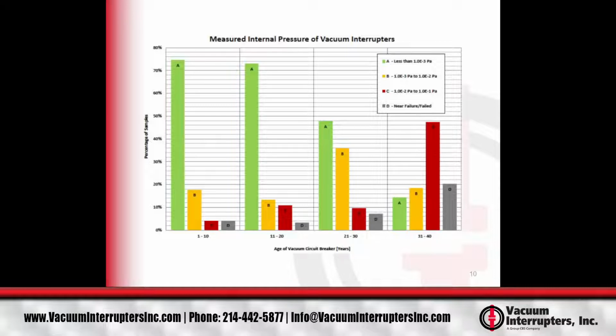on the bottom x-axis. For very young breakers, you have many good results. 1 to 10 years, many good results. 11 to 20 years, you still see many good results. After 20 years, you see a noticeable decrease in the very good pressures and a jump in the mid-range pressures. But after 30 years, you see a large increase in the number of high-pressure vacuum interrupters. This just goes to show that the 20-year shelf life may be a little conservative, and in reality vacuum interrupters, at least for this particular type, may last around 30 to 40 years, but we're at that point for many of the vacuum interrupters that are in the field today.